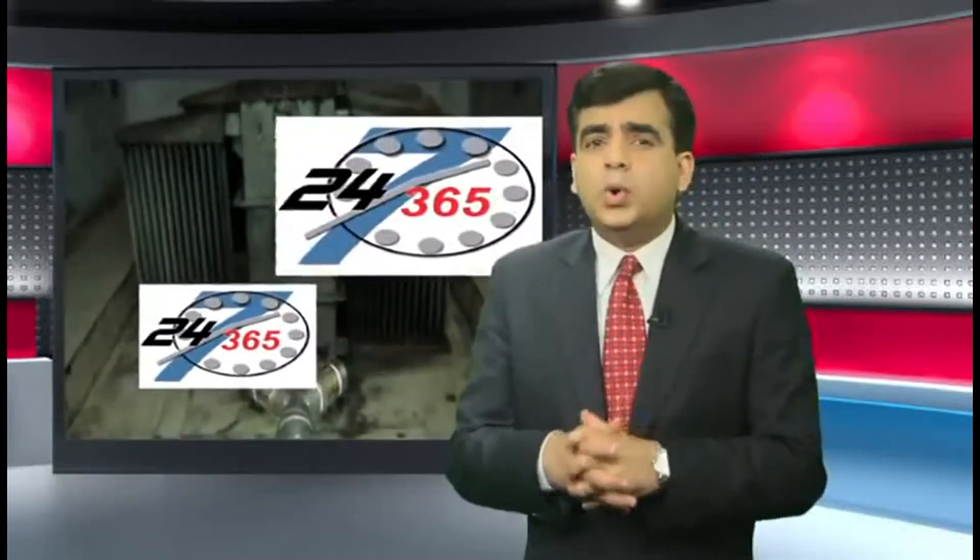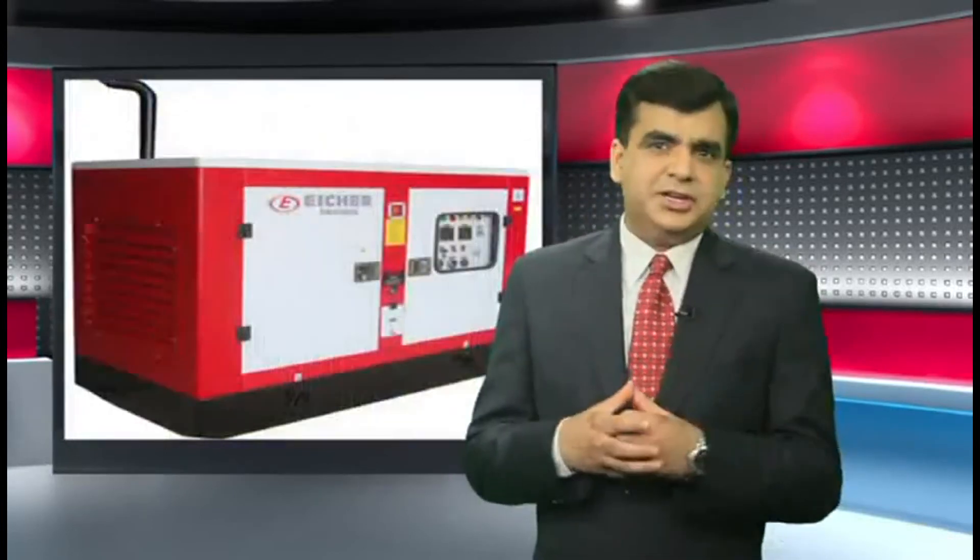The auto-quell system has many advantages. It works on A, B, C, electrical, and oil fires. It's self-contained and self-actuating, which means firefighting is automatic. The system is on 24/7 and has extended reach due to its flexible tubing to access all areas. It's also environmentally friendly, people friendly, and electrically non-conductive. It uses considerably less water than a conventional water-based system and evaporates completely in the fire environment, leaving behind no collateral damage. The system is also economical, because water as an extinguishing agent is cheap and maintenance requirements are reduced. The transformer auto-quell system is not just used to protect transformers — it can also be used to protect generators, genset canopies, and air-conditioning.